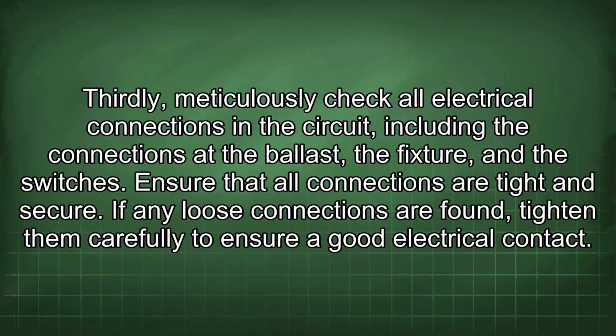circuits. Thirdly, meticulously check all electrical connections in the circuit, including the connections at the ballast, the fixture, and the switches. Ensure that all connections are tight and secure. If any loose connections are found, tighten them carefully to ensure good electrical contact.